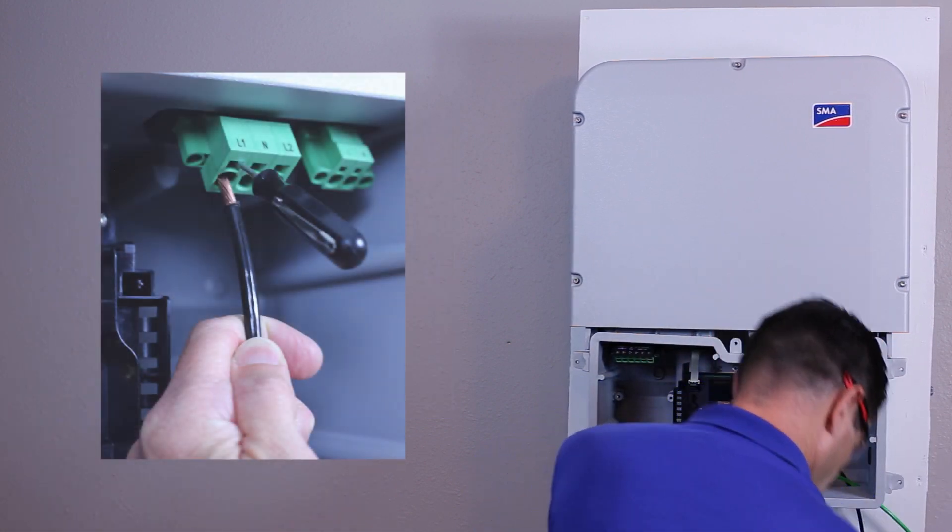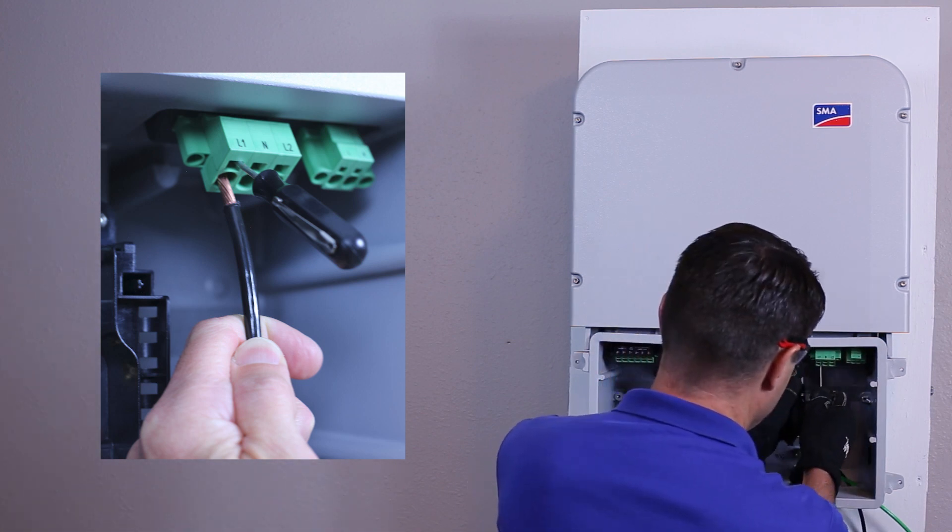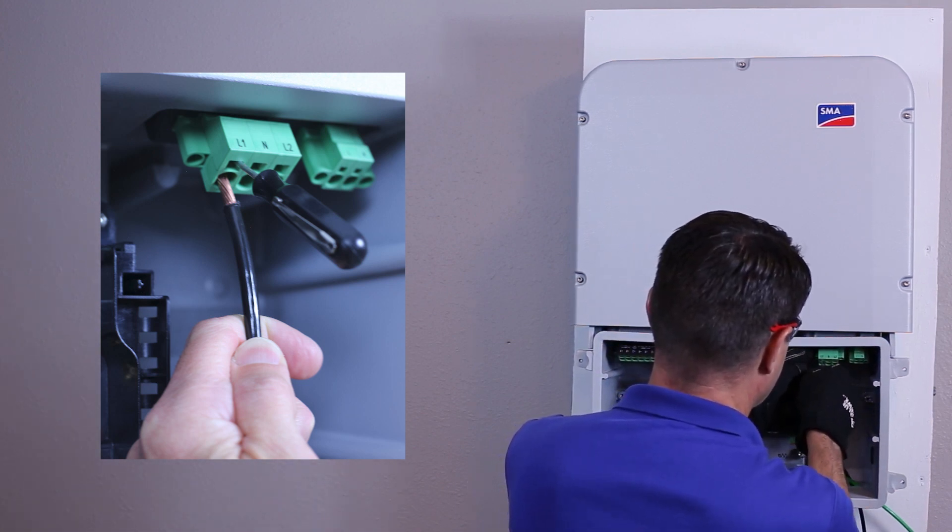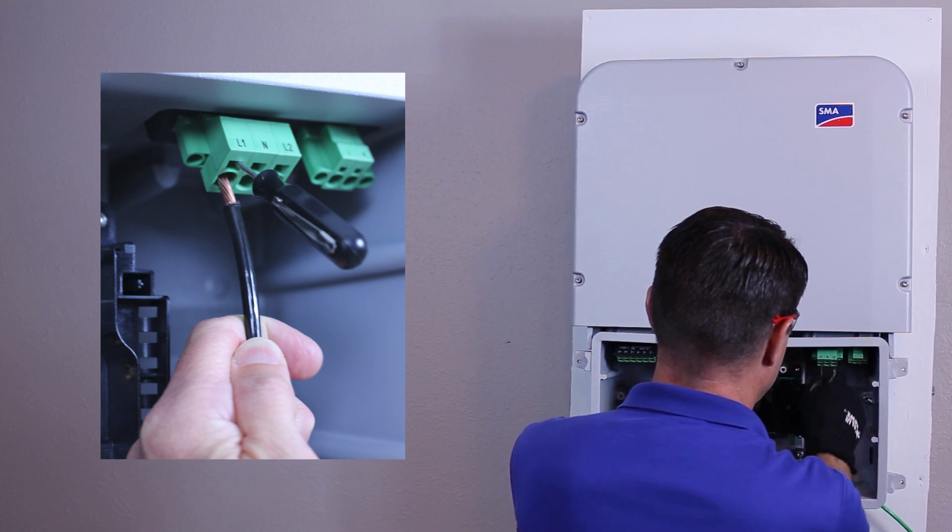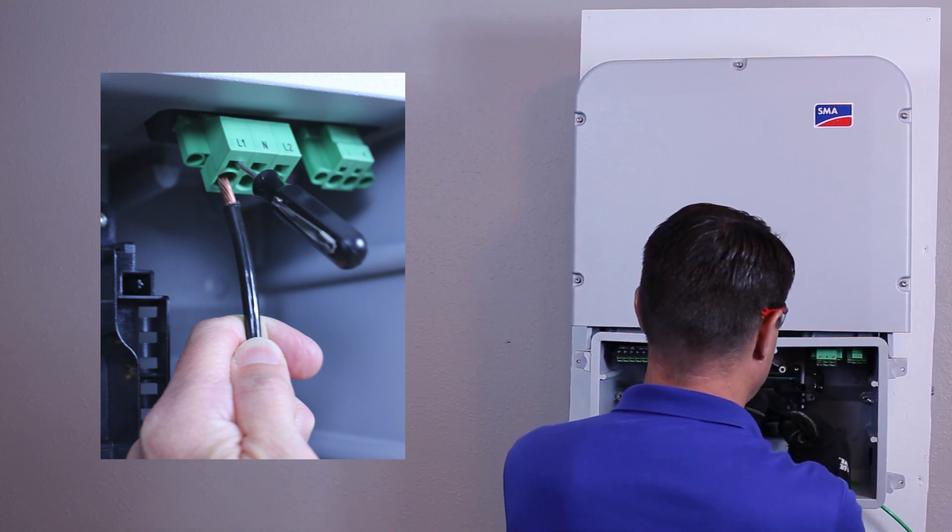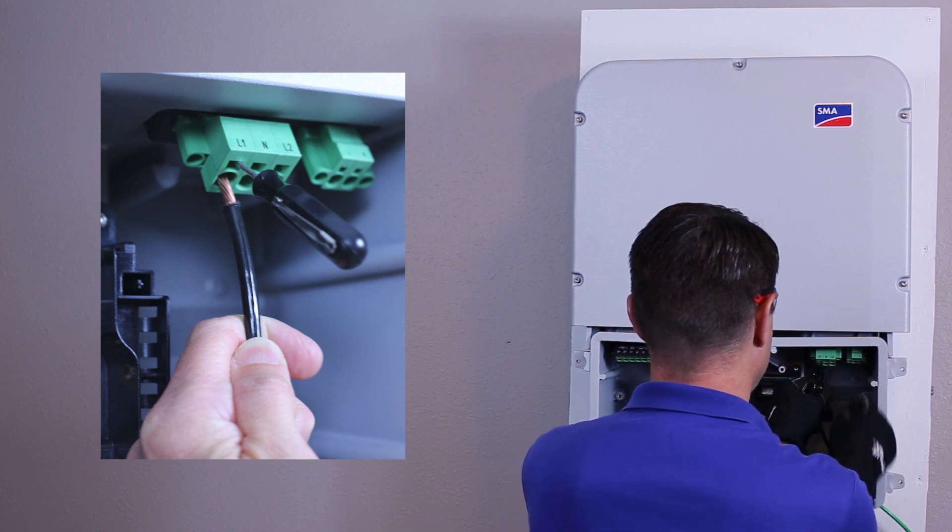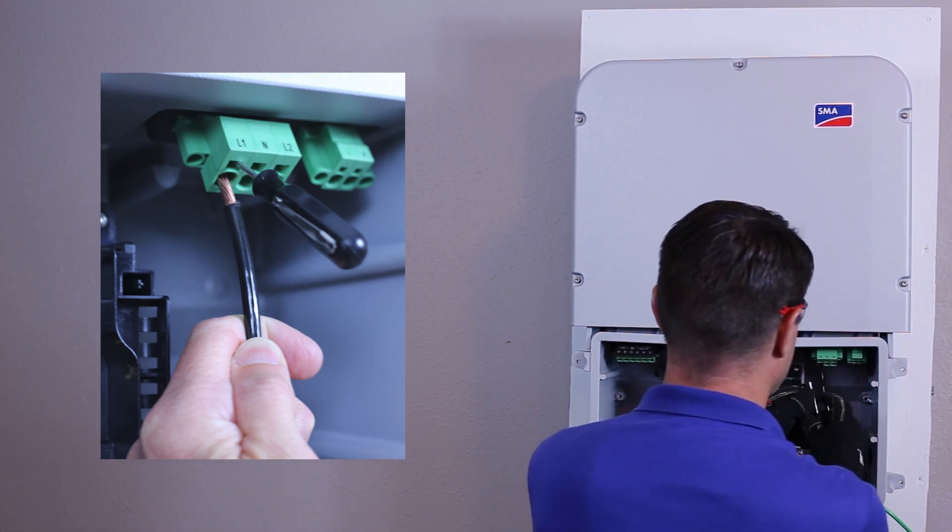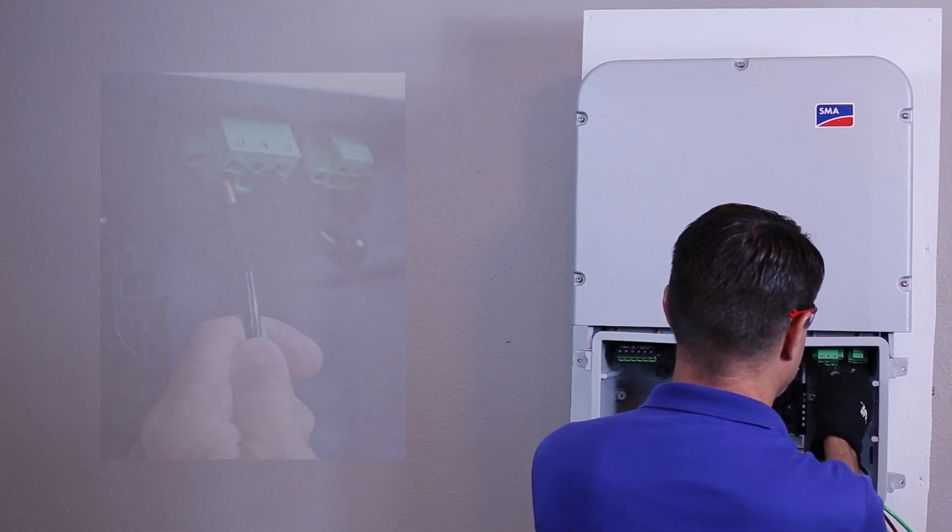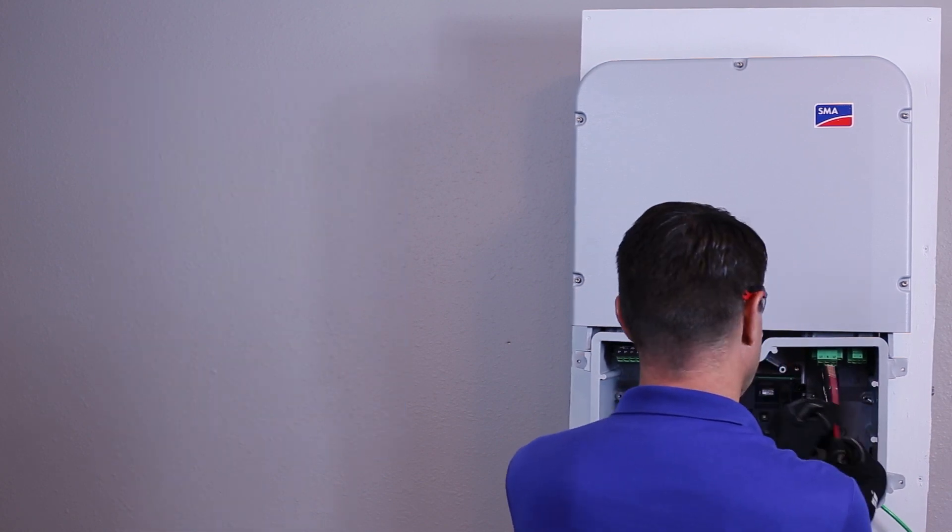When inserting the conductors into the AC and DC connection plugs, ensure that only the round holes at the back are used. A 5/32 inch standard screwdriver can be inserted into the small rectangular probe measurement port in front of the round hole to open the clamping terminal. This ensures no strands of the conductor are folded back when it is inserted. Remove the screwdriver and ensure the conductor is securely held.